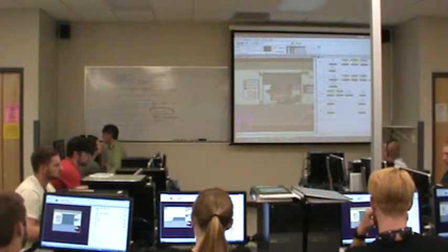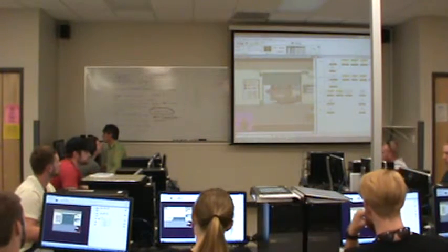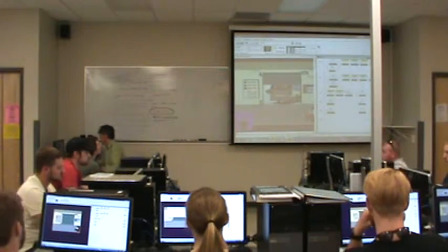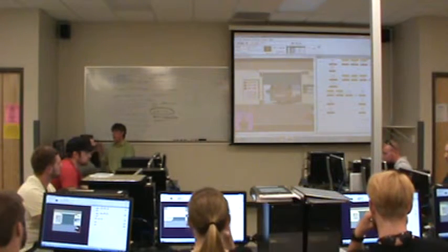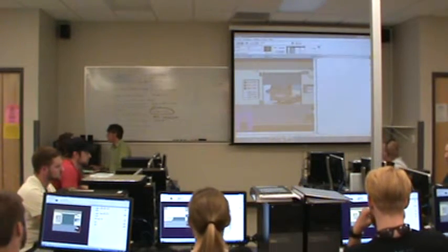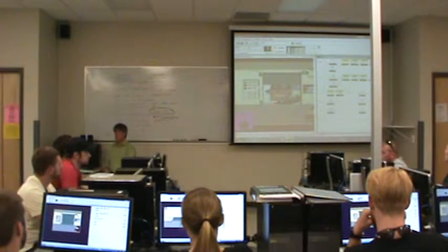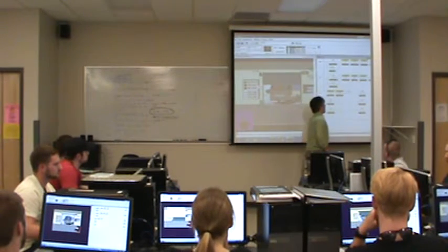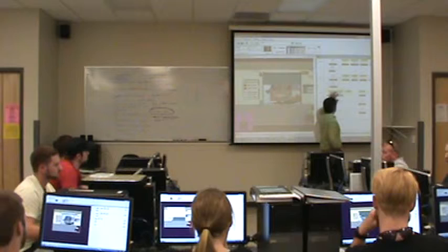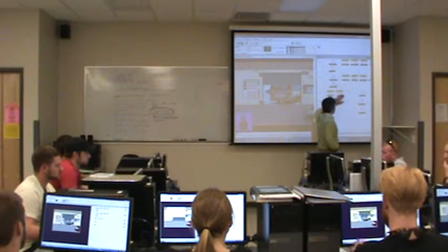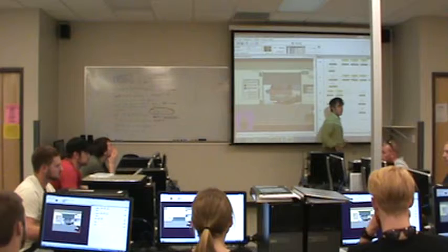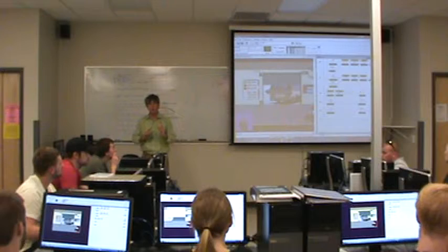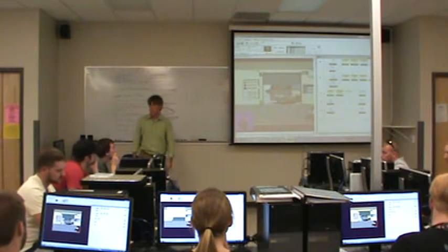Okay, I can turn down the scan speed, but that's just playing with the clock rate of the PLC. So what I'm going to do is change this to bit 8, because bit 8 will flash at half the speed of bit 7. Download that, run it. That looks pretty decent. You see what I'm doing? All I'm doing is using a bit in memory that I know is turning on and off to kind of block this. So these conditions are true, but this blocks it every now and then so that the lamp flashes. It's a nice little trick to know that. If I needed a random number, I could go and take all 16 of those bits and generate a pretty decent random number. Okay?